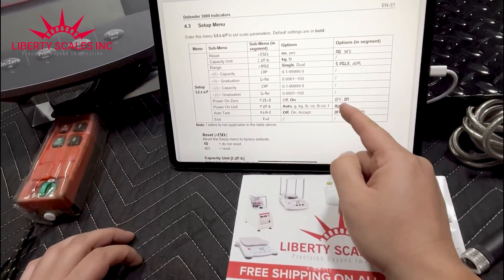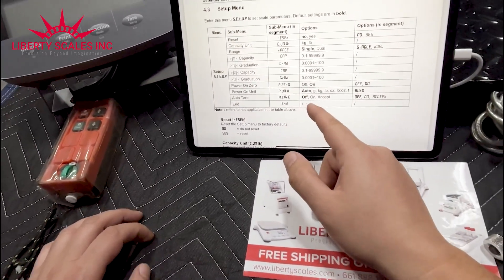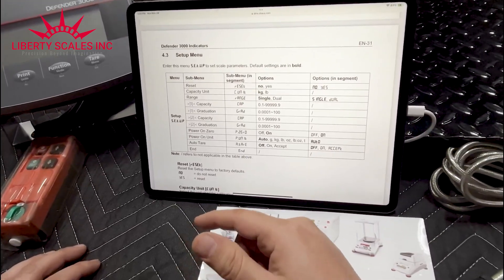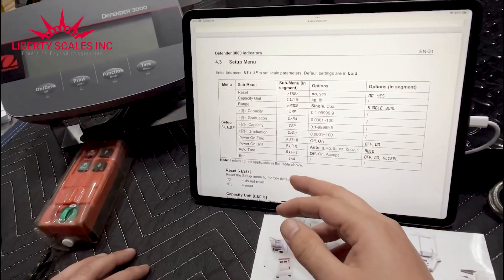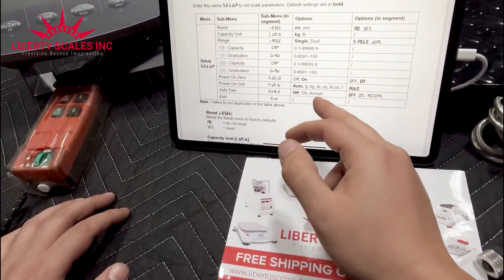We put auto for unit, so that just leaves it at the last unit you left it at. Auto tare — some applications have something on the scale when they turn it on and don't want to count that, while others do want to count it. So the options are off, on, or accept.